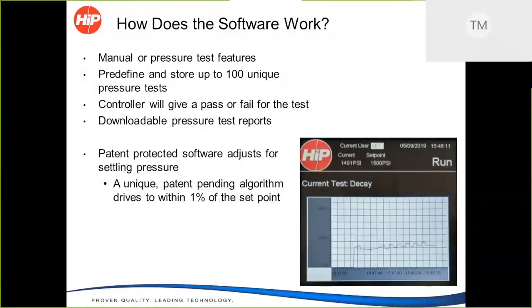What we can actually do is we have a very unique algorithm that'll run through a series of pressure ramps and decays, and we can lock in on that desired pressure point within 1% of the set point. Once we achieve that, then we'll start that pressure decay test, and we can watch the pressure slowly decay over time. So it's a really accurate way to do that test, and it's also very easy to set up. So it takes a lot of the guesswork out of doing a pressure decay test.